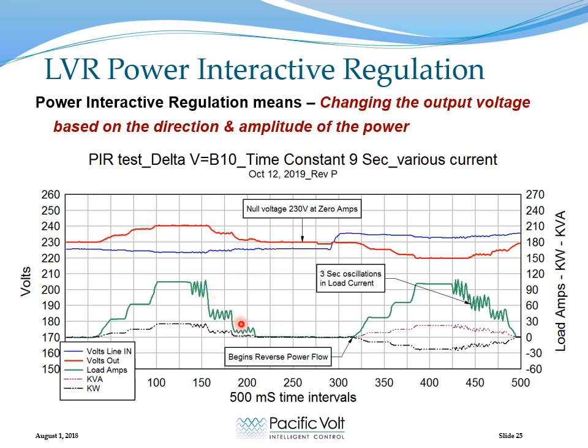The current then reduces and drops back to 0. The power flow is also 0 at this point. The regulator voltage drops to the null point. At this time, the power reverses. You can see we have negative power now, and as the current increases, the output voltage of the regulator decreases. So it is compensating bidirectionally for the current flow in a way that offsets the rise or fall of voltage due to the system impedance.